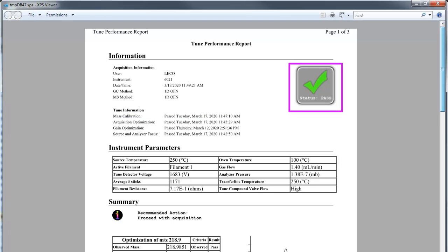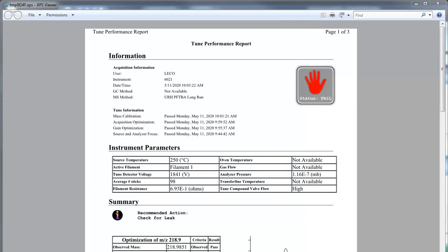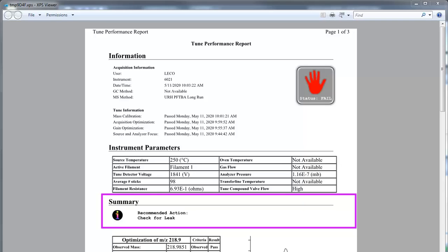A status icon in the upper right corner displays whether the tune performance criteria have been met. A green checkmark with the status pass indicates that all of the tune criteria have been met. A red handprint with the status fail indicates that one or more of the tune criteria have not been met. Recommended actions to improve the system will be listed below in the summary. The action will advise the user on how to improve system performance.